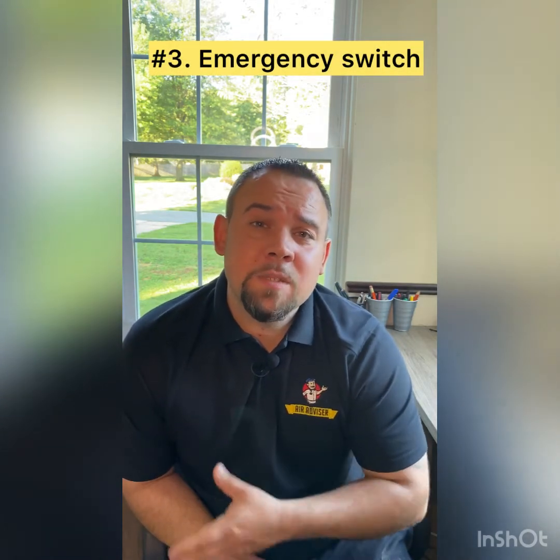The next really simple thing that we see all the time is the emergency switch at the top of your basement stairs. A lot of times when a child or even an adult is coming up the stairs and turning out the lights, fumbling around on the wall to feel the light switch, they accidentally hit the emergency switch that kills the power to the furnace downstairs. Now, yes, the furnace is connected to the air conditioner. They are interrelated. So if you do kill the power on that switch, you will kill the power to your furnace, which will not allow your AC to run.